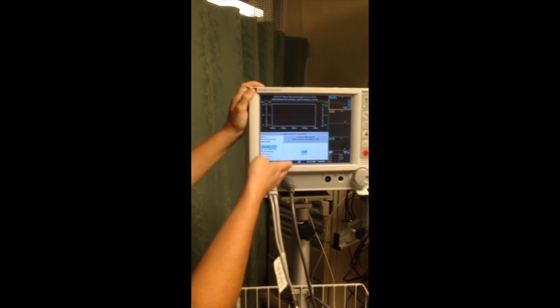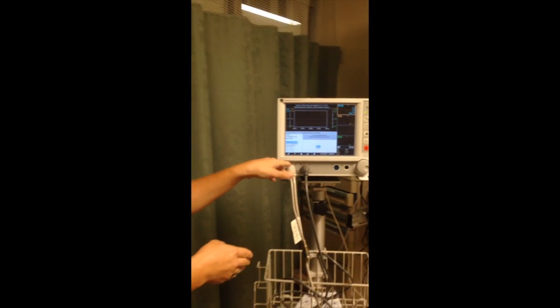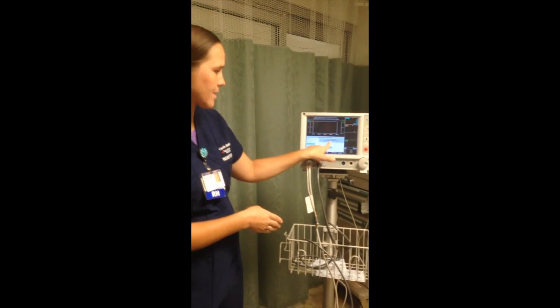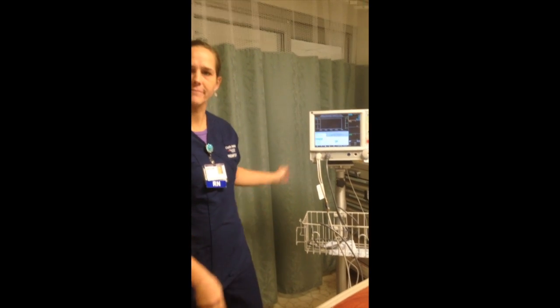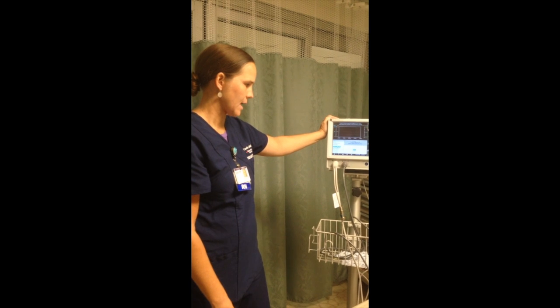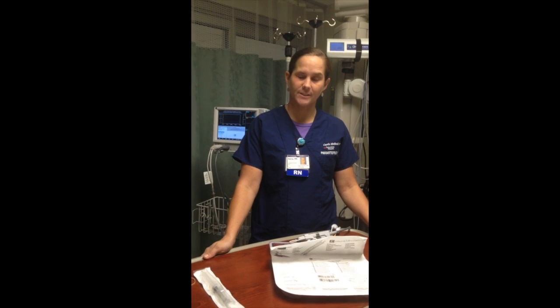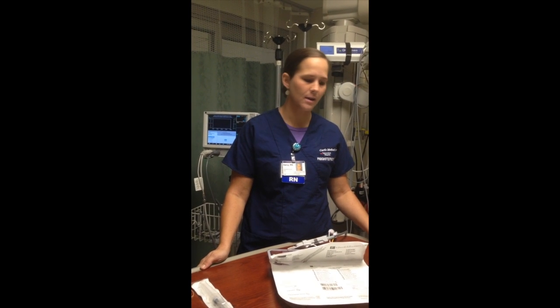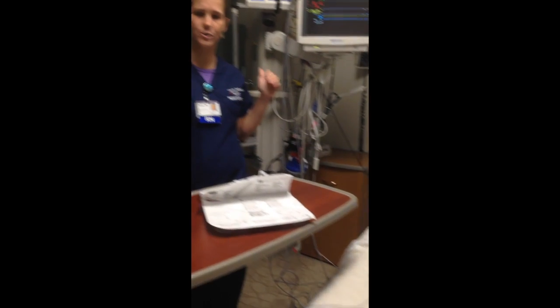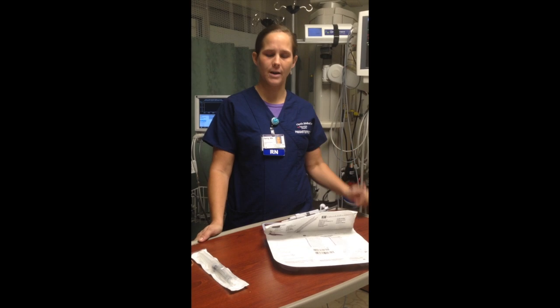At this point, our in vitro is finished, and once it says insert catheter, then select start. So now the physician is able to insert the catheter. Once it's in, you can hit start, and you'll get your numbers automatically. At this point, you are ready for the physician to come in. You've told him that you're ready. You have your pressure cables zeroed and set up. You have your SVO2 set up, calibrated, ready to go.